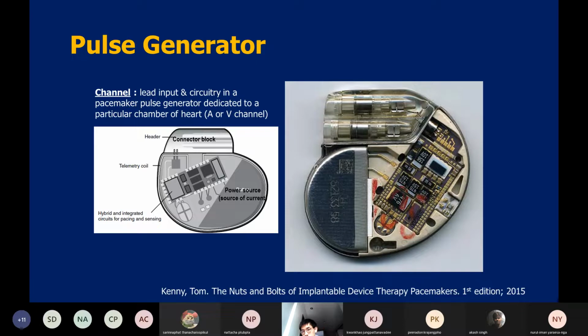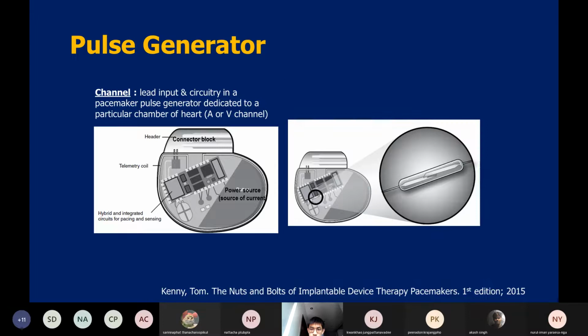This is what the real generator looks like. The generator has this part called the reed switch. When you apply a magnet onto the pacemaker, the reed switch switches the pacemaker into magnet function. I will explain it later in this session. What is the magnet function in the pacemaker? Every pacemaker has this reed switch. So if you put a magnet on the pacemaker, even when it is programmed in any mode you have set before, it will switch into a magnet program.